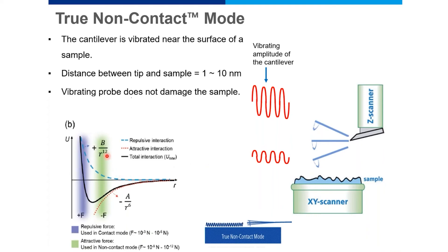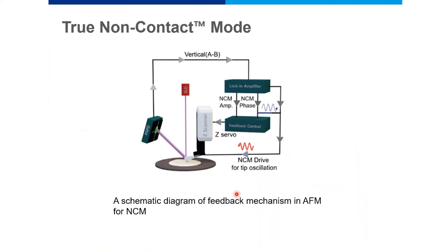In non-contact mode, the cantilever operates in the long-range attractive force regime. The cantilever is just a couple of nanometers above the sample surface and tracks that surface. Depending on the change in amplitude, an image of the sample surface is generated. Whenever there is a change of amplitude, the feedback mechanism tells the Z-scanner to move slightly up or slightly down to maintain the set-point amplitude given to the cantilever.